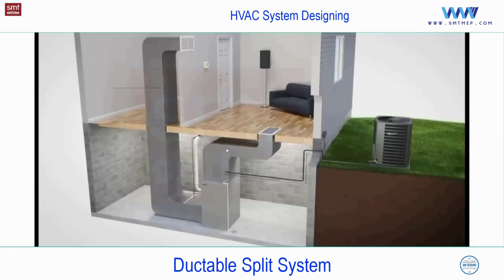So you can find here, this is a supply duct and this is a return. And you see this position of the duct; in actual practice, we are not generally supplying the cool air from the floor. This concept is basically from a heating point of view. So even for the air distribution, don't draw a conclusion. We have a separate topic for distributing the air. As per standard, we supply the cool air from the higher level and the hot air from the lower level. There is a reason, which we'll discuss at the time of the air distribution topic.